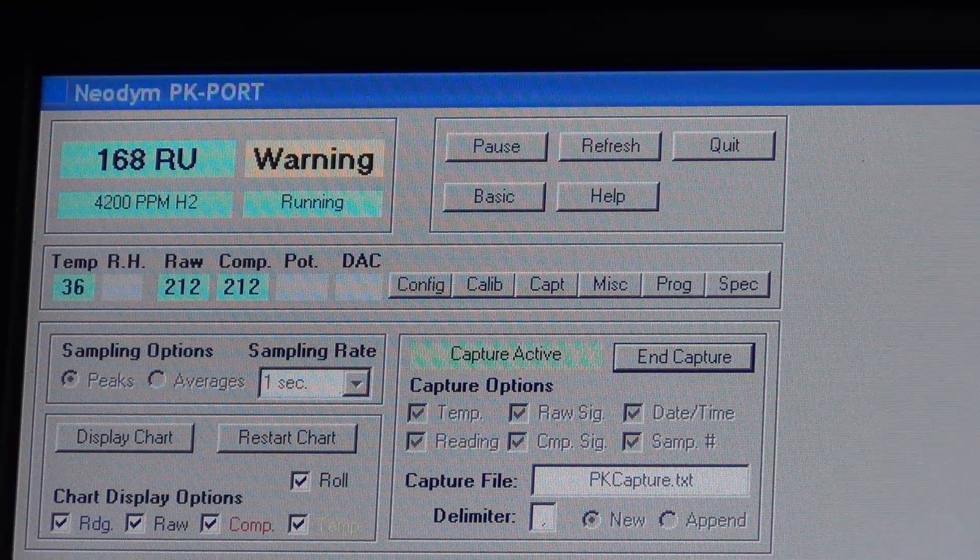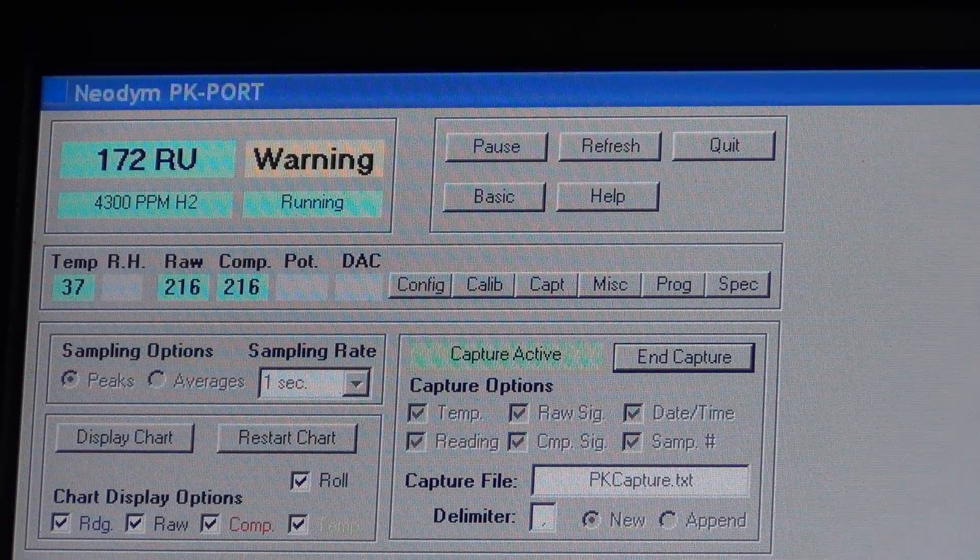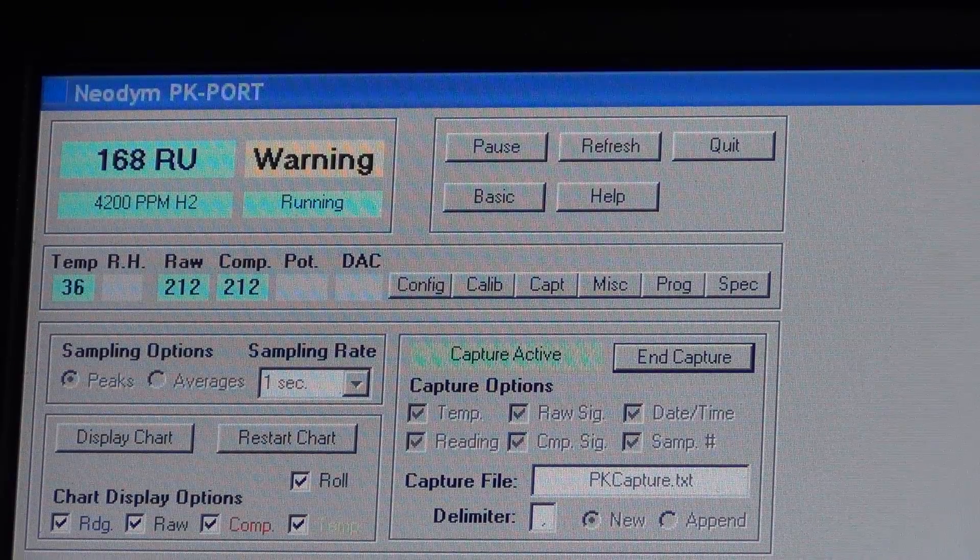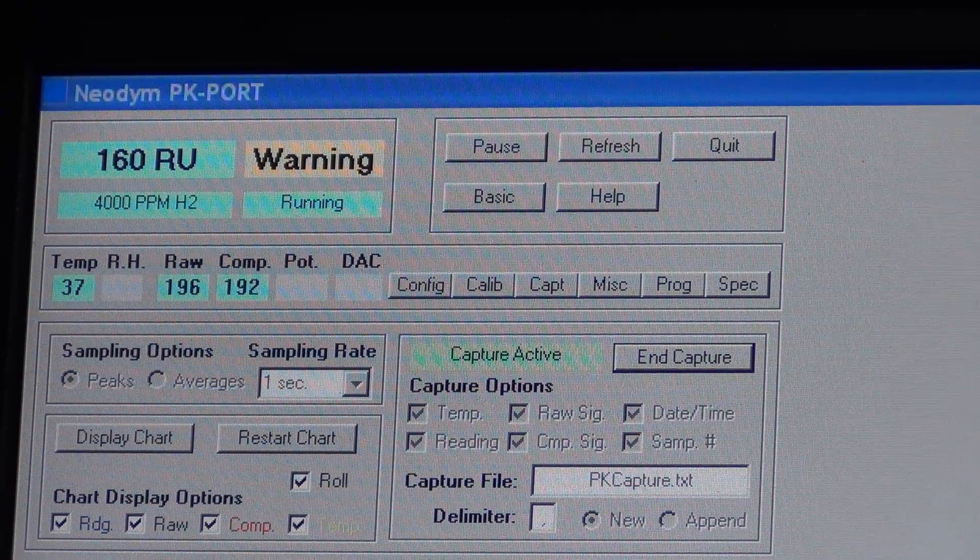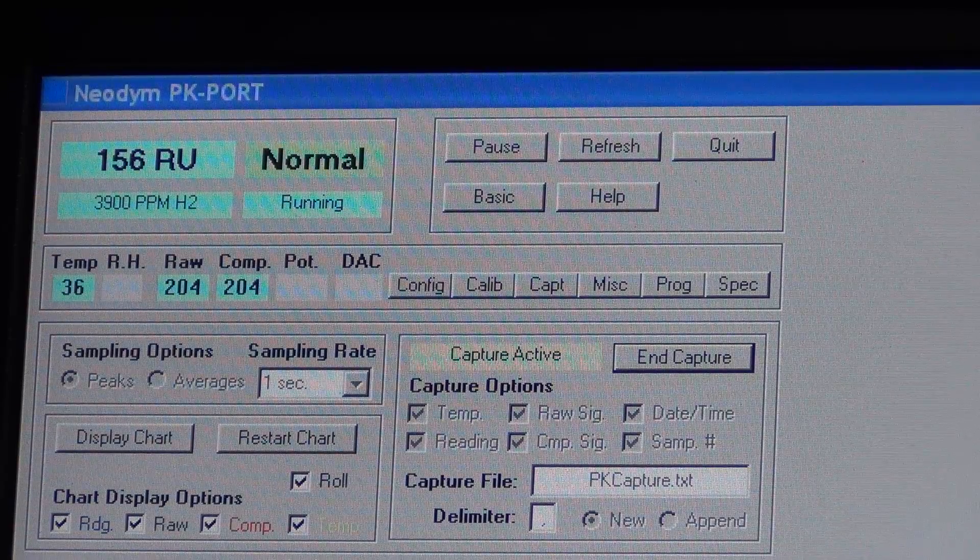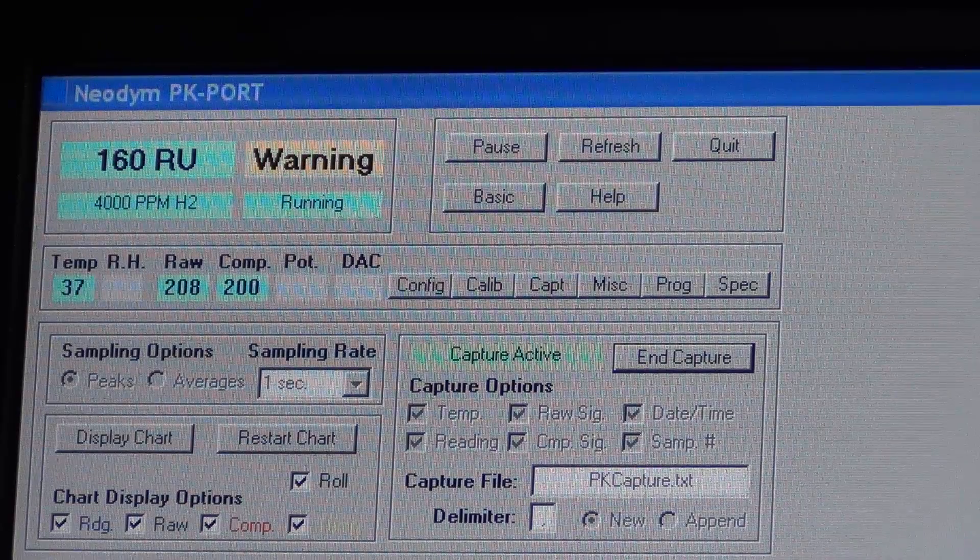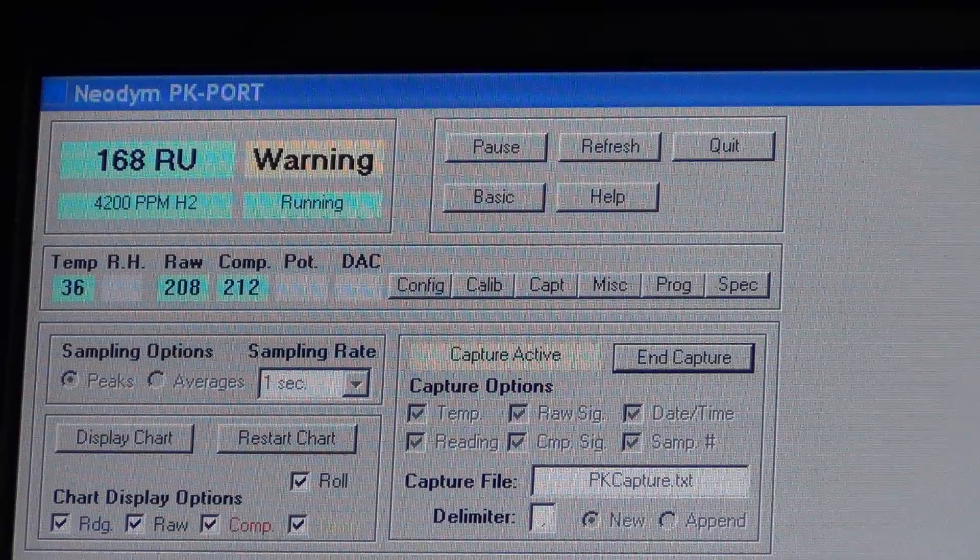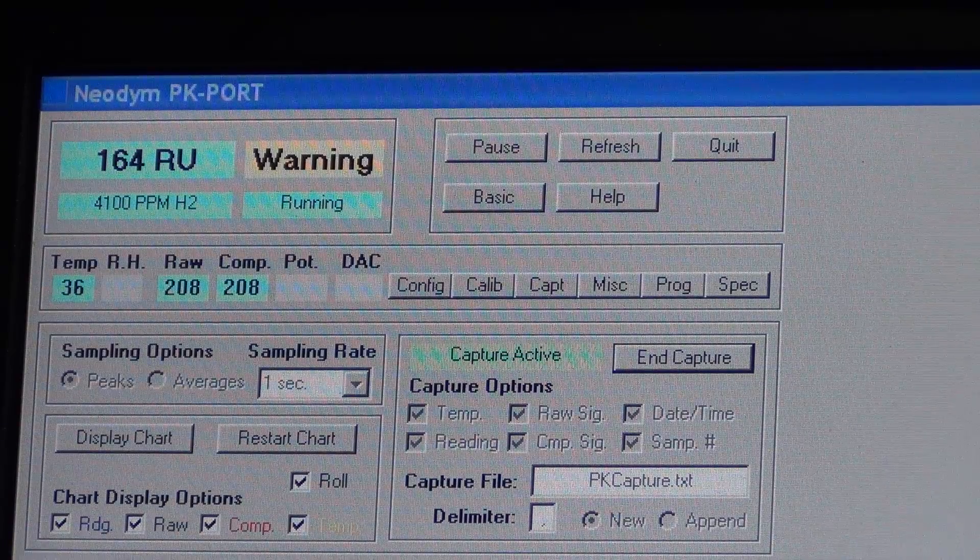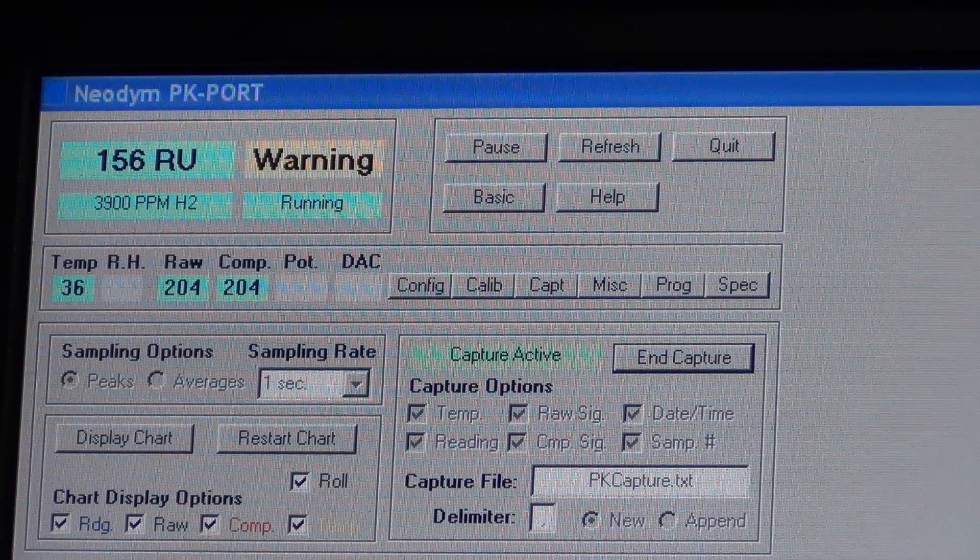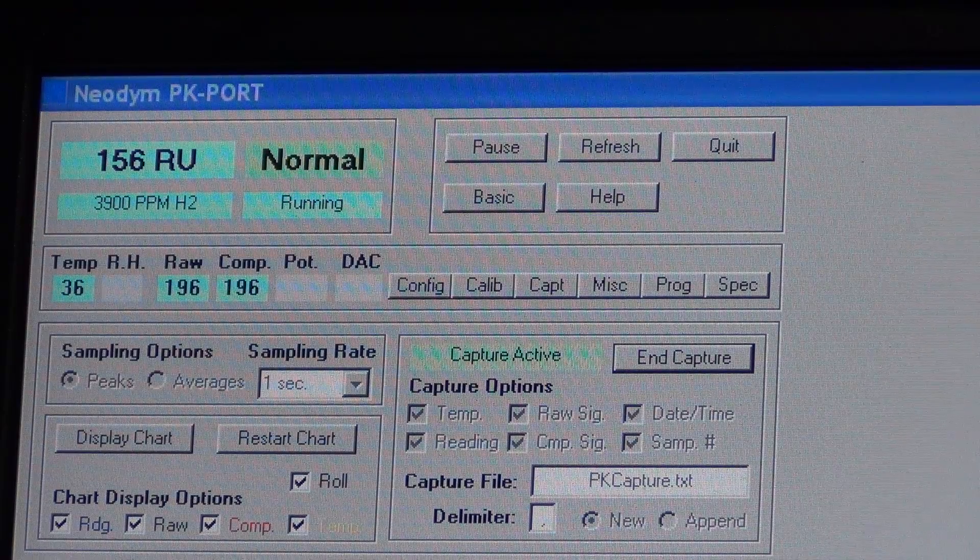So that's pretty what I wanted to show. And the ventilation is working and batteries do give off hydrogen gas if it's totally sealed. And when you're doing at least close to the absorption stage, which in our case was 59 volts, it went up pretty quickly. So I would say it's a good idea in our case to actually have this vent and check and make sure it's working. So anyway, I wanted to share that and thanks for watching. Bye.